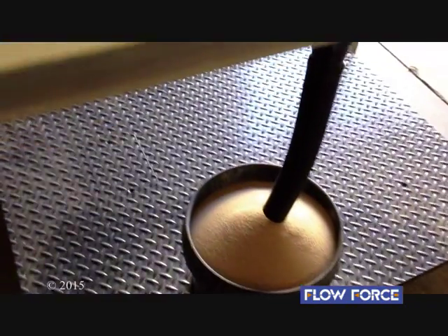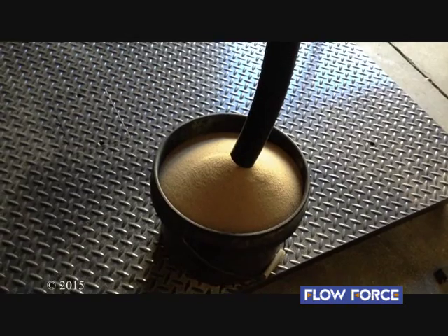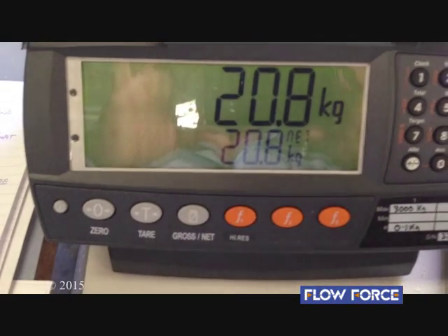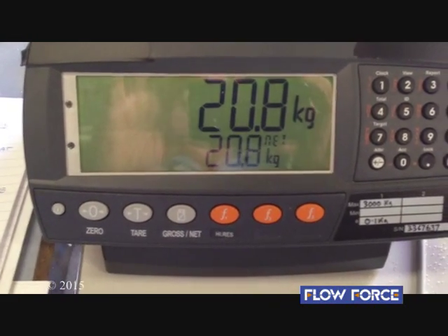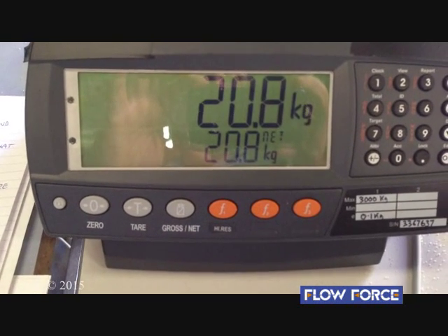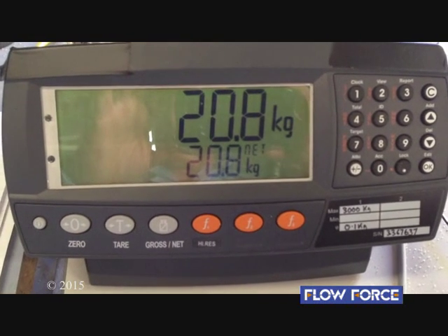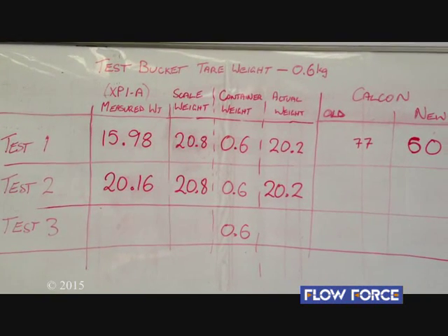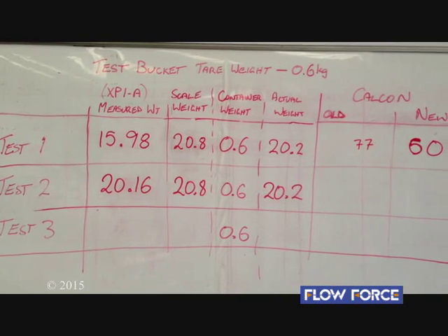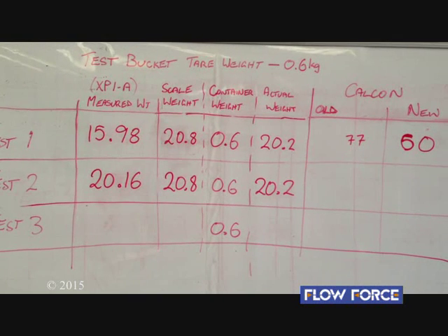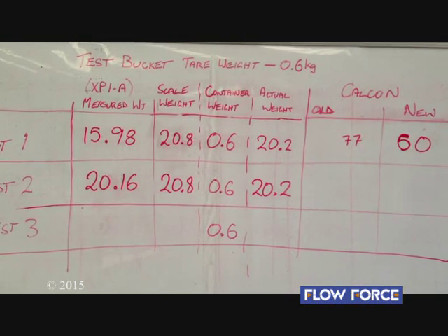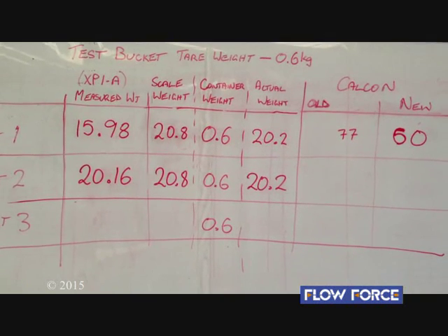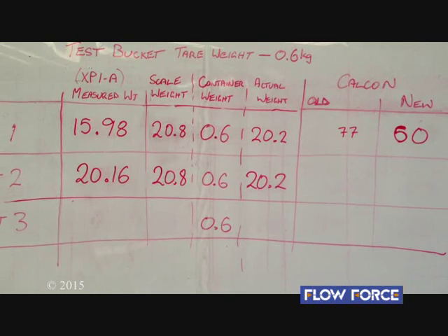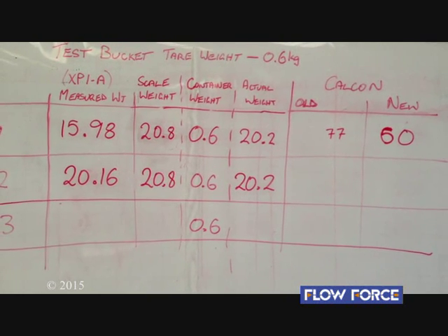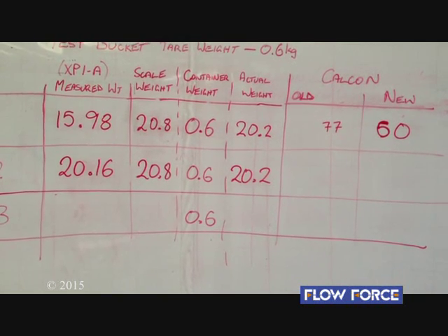We'll now weigh our container, and we see that comes in at 20.8 kilograms. So we'll note these figures on our calibration sheet and do the edit calibration process again. So test 2, XP1 controller reads 20.16 kilograms. Our scales for our test weight is 20.8 minus the 0.6 for the bucket, leaves us an actual weight of product of 20.2 kilograms. We'll now put that figure into the XP1 controller, and we should get a new Calcon.